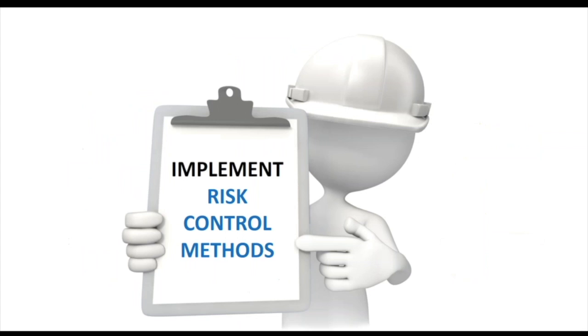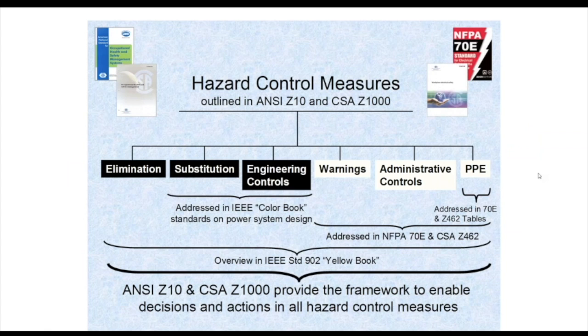So implementing the risk, this is the third step from CSA Z1002, but it does have major impact back to the electrical part, which is what we tried to do in our Z462 committee. This is one of the standard ones, used many times. You'll see the Z462 and the NFPA 70E, the ANSI standards, and the hazard control measures. This slide should probably be updated - it should say risk assessment measures. It's an older slide, but it still points out very well.